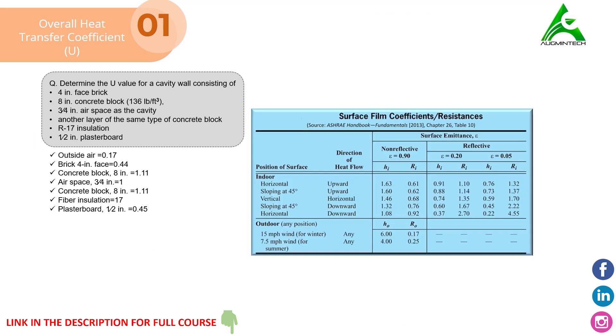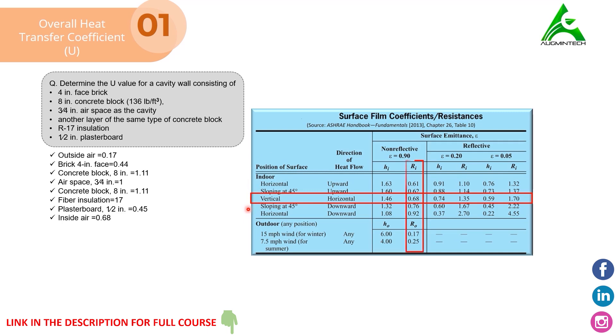Finally, we find the resistance of the inside air. We use the same chart as for the outside air, this time selecting the section for indoor conditions. On selecting the suitable row and column, the value of resistance is found to be 0.68. So the resistance of the inside air film is 0.68.